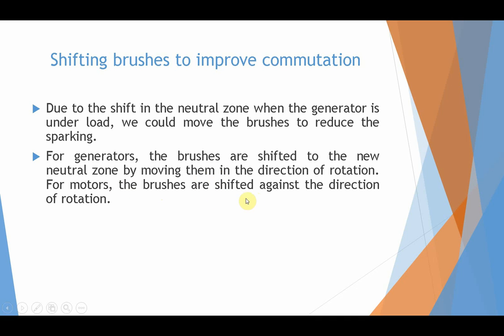For a motor, the brushes are shifted against the direction of rotation in order to improve commutation due to armature reaction. We need to move the brushes to the new neutral zone — in the direction of rotation for generators and against the direction of rotation for motors. This is a theoretical concept; practically, we make other arrangements that we will study in the current classes.